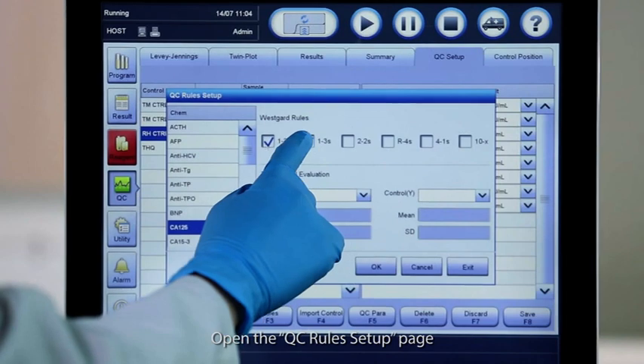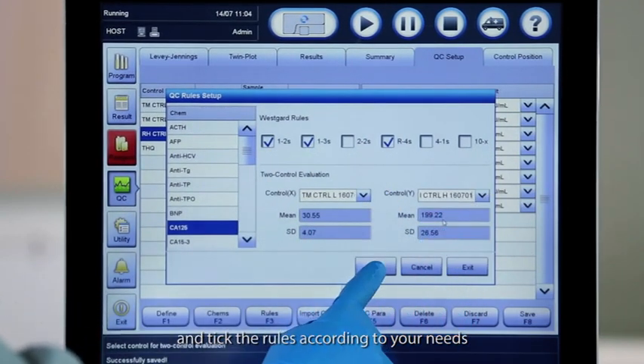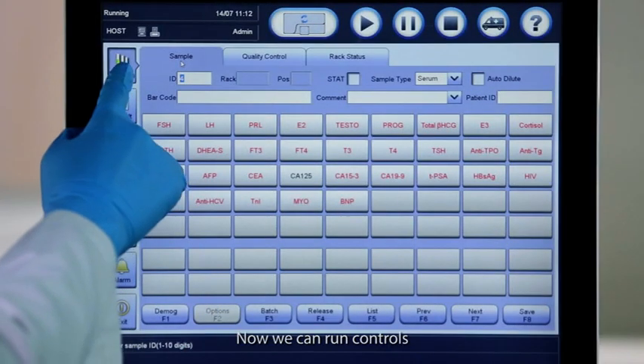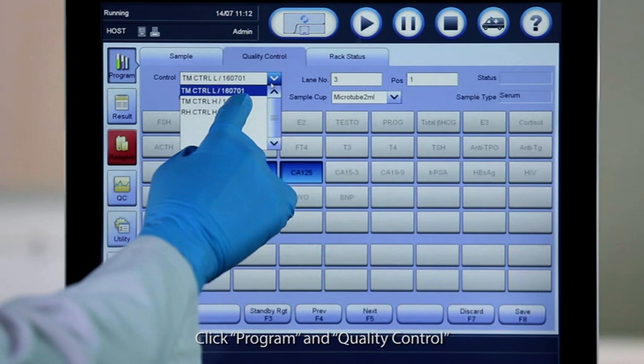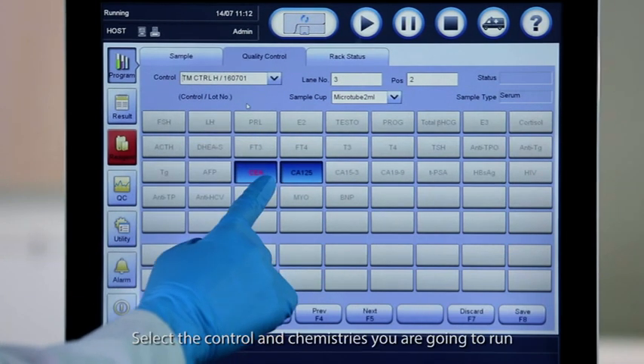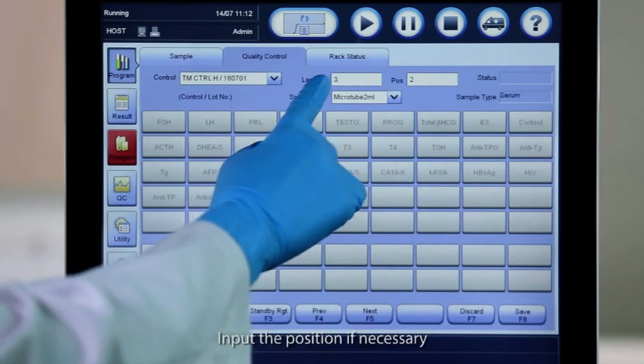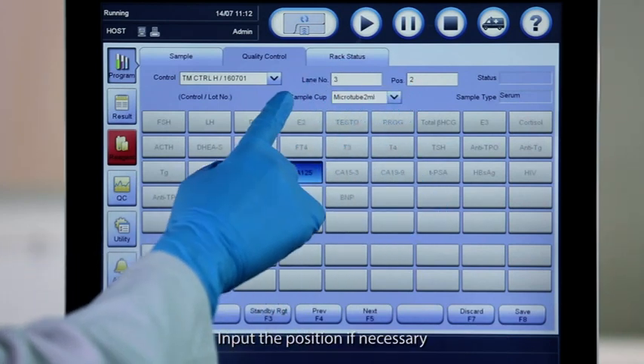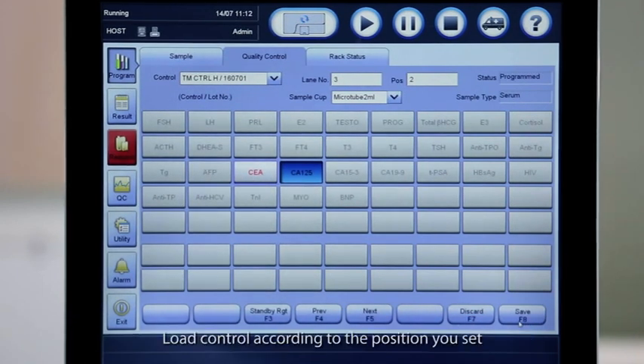The software allows you to set up QC rules. Open the QC Rules Setup page and tick the rules according to your needs. Now we can run controls. Click Program and Quality Control. Select the control and chemistries you are going to run. Input the position if necessary. Choose the sample cup type used. Load control according to the position you set. Click Start button to run.